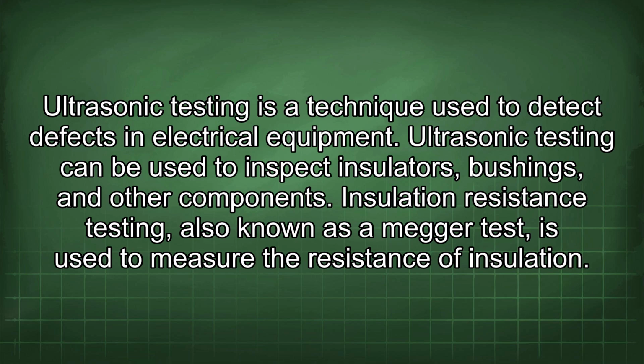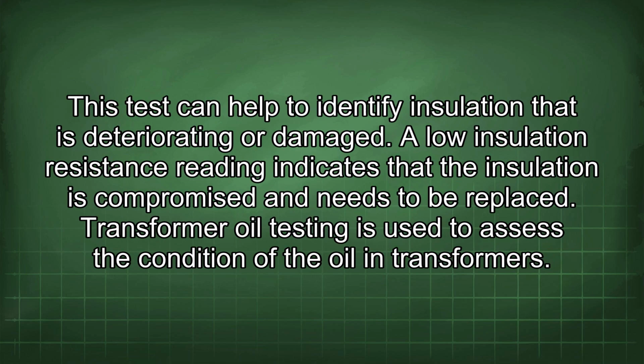Ultrasonic testing is a technique used to detect defects in electrical equipment. Ultrasonic testing can be used to inspect insulators, bushings, and other components. Insulation resistance testing, also known as a megger test, is used to measure the resistance of insulation. This test can help to identify insulation that is deteriorating or damaged. A low insulation resistance reading indicates that the insulation is compromised and needs to be replaced.